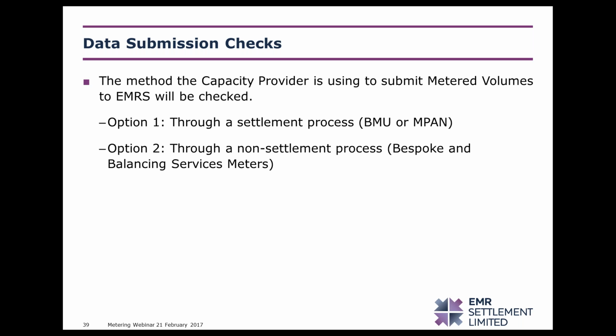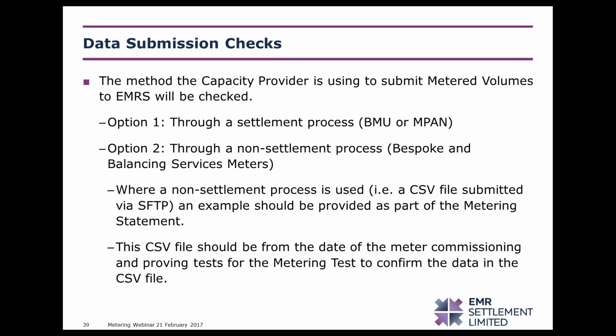If you are going with option 2, which is bespoke and Balancing Services Meters, you will need to provide data via a non-settlement process, i.e. the CSV file. An example of the CSV file should be submitted as part of the metering statement. Please note that this CSV file should be from the date of when commissioning and proving tests were carried out for the meter.